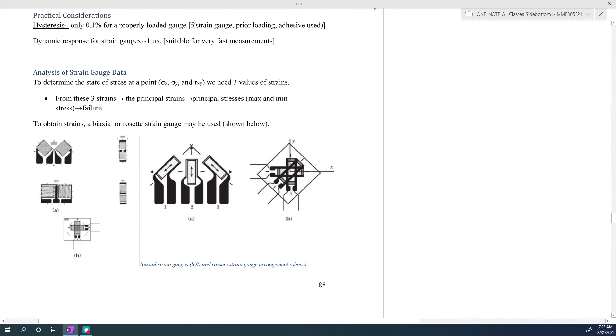Some things to consider when we're talking about strain gauges is hysteresis and dynamic response, basically loading and unloading of strain gauges. If the gauge is properly installed, the only hysteresis can be as low as only 0.1% of your error, so very low in terms of the percent error, which is good. Hysteresis is not a major issue if the strain gauge is properly installed.